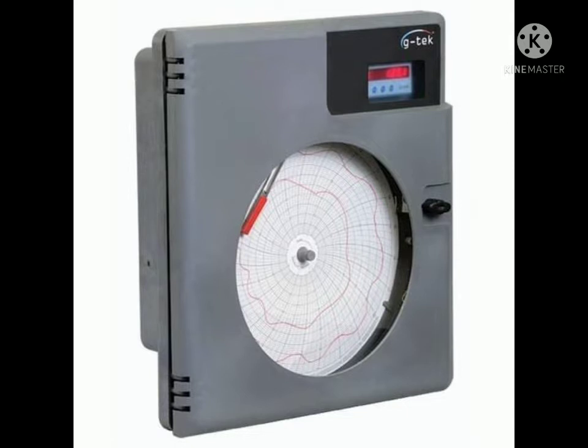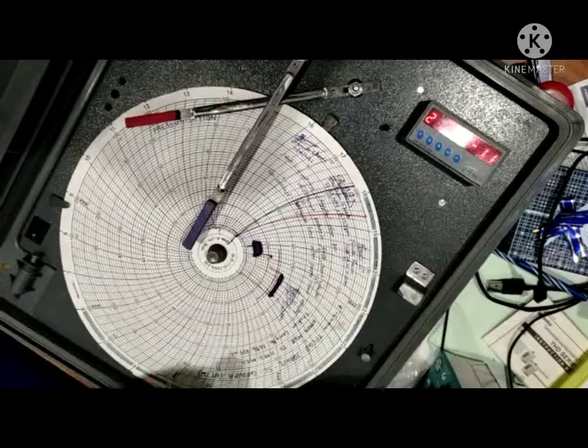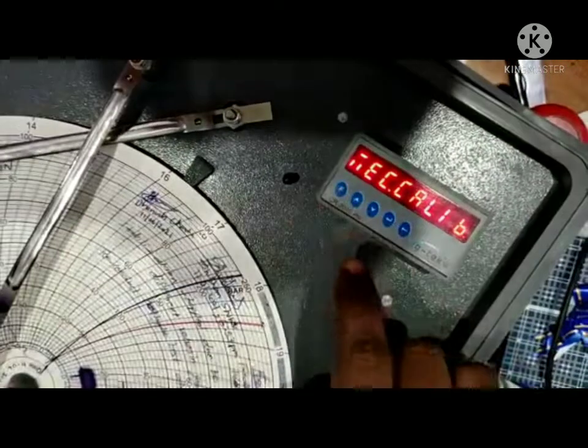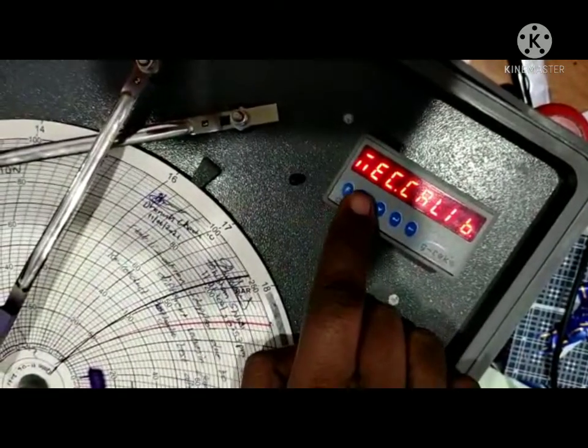Hi all, in this video we will see the mechanical calibration, that is the pen zero and span calibration of a G-Tek circular chart recorder. Press the up and down key at the same time to enter the mechanical calibration mode.